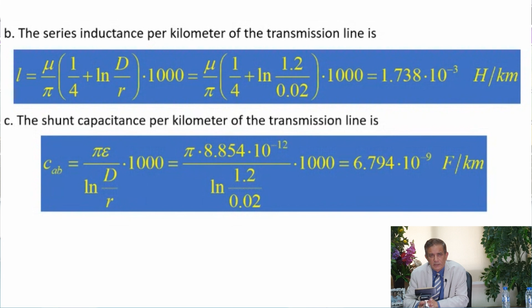For the series impedance of the transmission line, we have R and L. Multiplying L by omega, which is 2 pi F, gives X or XL, and both values have been calculated. So impedance is R plus jX, with R from the first step and X from L multiplied by omega. Remember that R and L are always given per kilometer, as in manufacturer data sheets. With a total line length of 30 kilometers, we multiply by 30 to get the impedance in ohms. This is the series impedance of the transmission line.